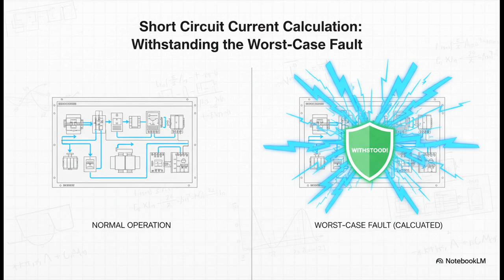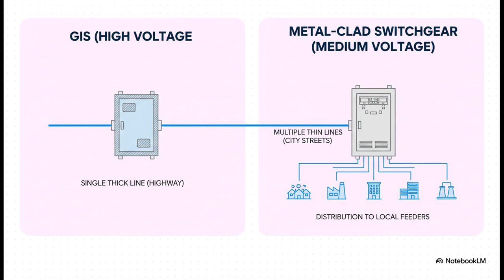Okay, so once the power has been stepped down and managed by the GIS, where does it go? It goes right over here, to the 13.8 kilovolt Metal-Clad switchgear. So if the GIS is managing the high-voltage superhighway coming in, this switchgear is managing all the medium-voltage city streets going out. It uses regular air for insulation and has rows of individual circuit breakers, each one protecting a specific feeder line that powers a neighborhood or a big factory.